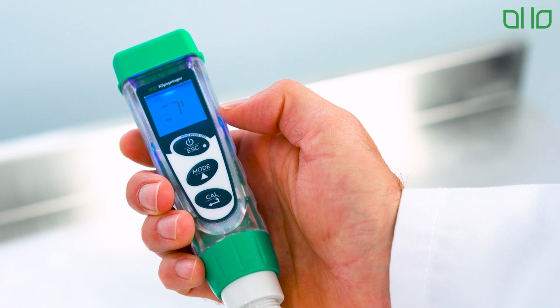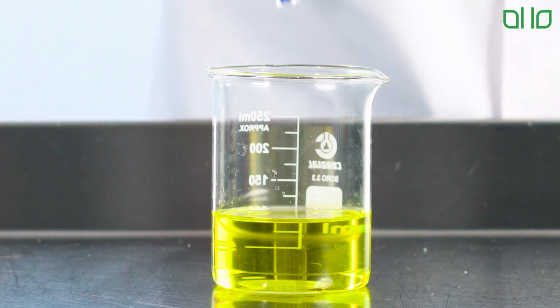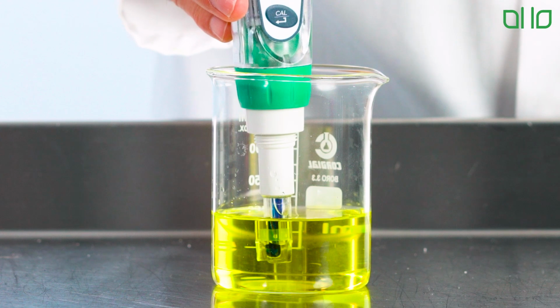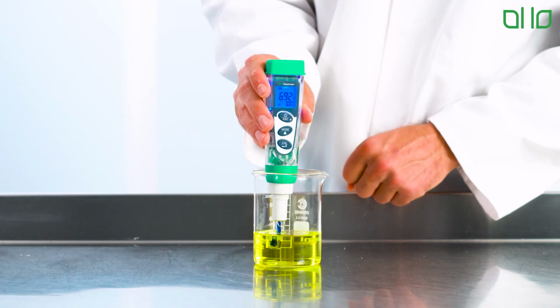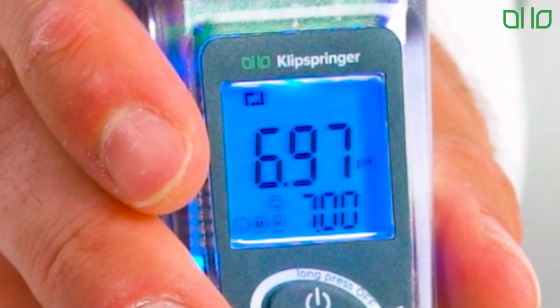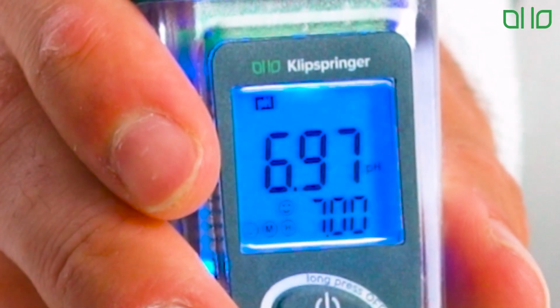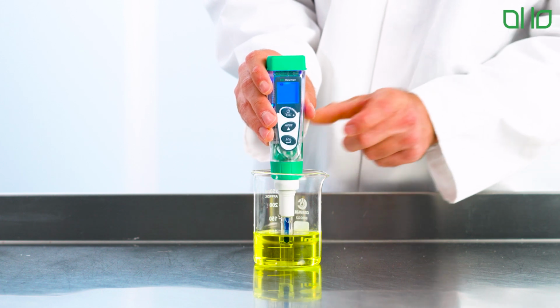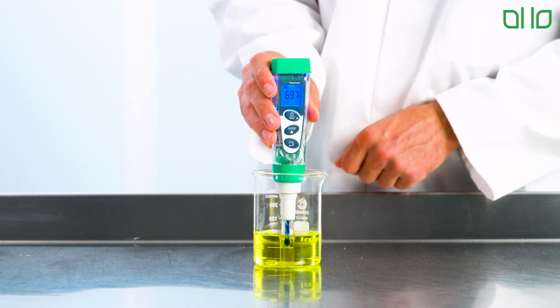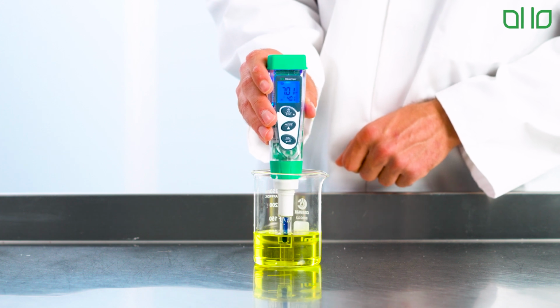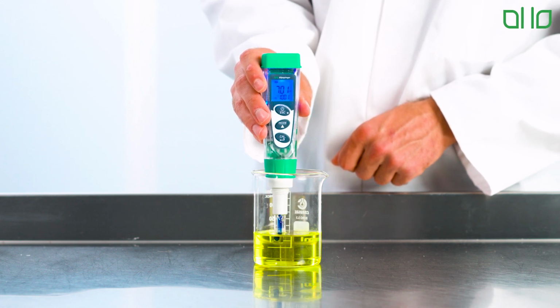Place the probe directly into the pH 7 buffer solution. No stirring is needed. Hold the probe steady in the solution until a small smiley face appears on the screen. This indicates the reading has stabilized. Once the smiley face appears, press the Calibrate button to record the calibration. Be patient, it may take a few seconds for the reading to stabilize.